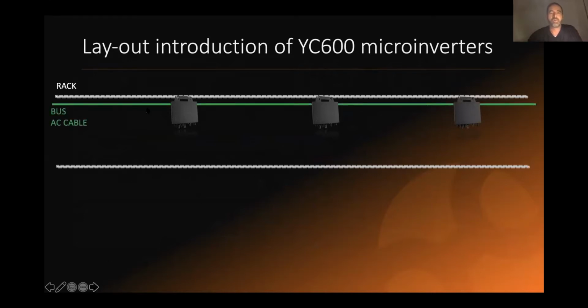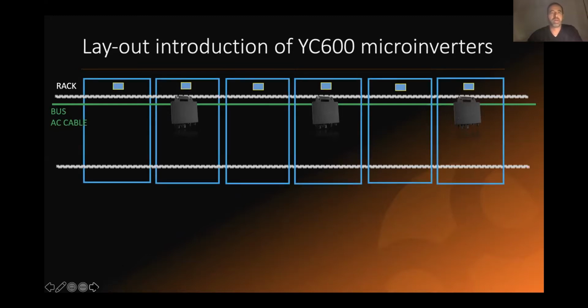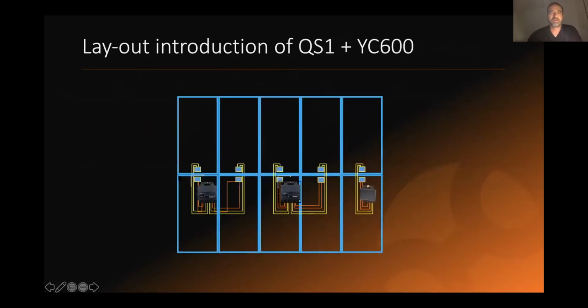Then you put the bus cable. So basically, you have the 2 DC pairs, an AC output, and then you have a bus cable, an AC bus cable running along with drops or connectors every 2 meters or 4 meters to connect and plug in the AC. One side will go to the junction box and to the AC box at the end. You put the panels, you connect the junction box to the DC input, click, and you're good to go. Then you connect the DC connectors.